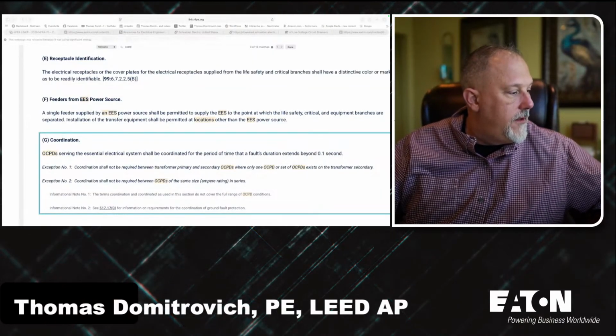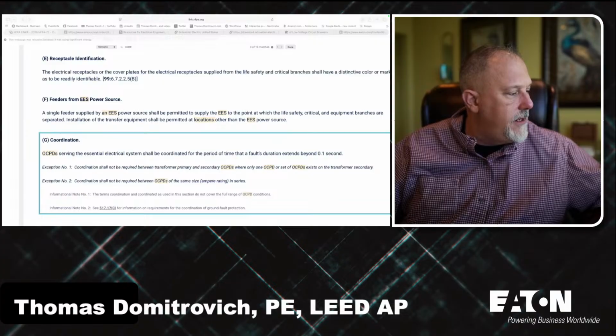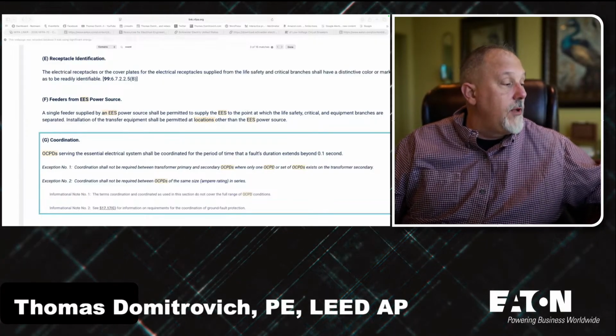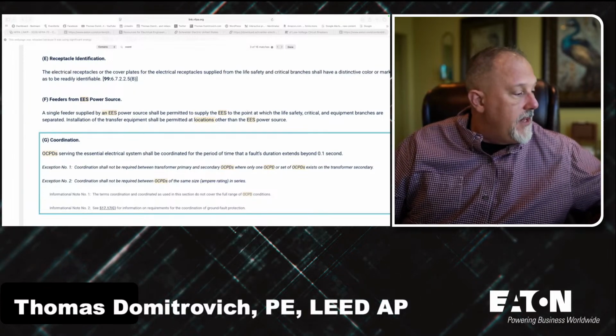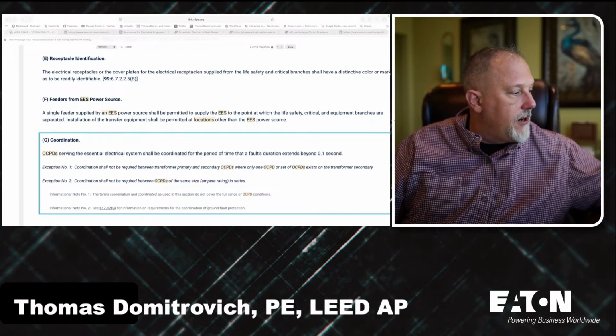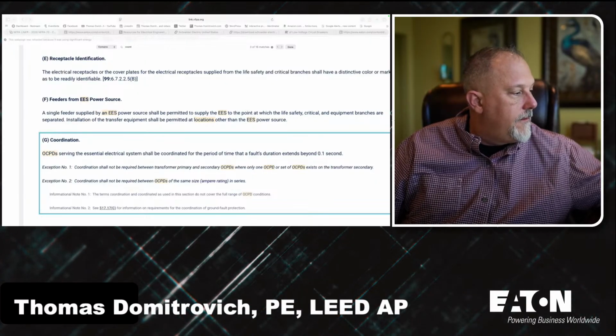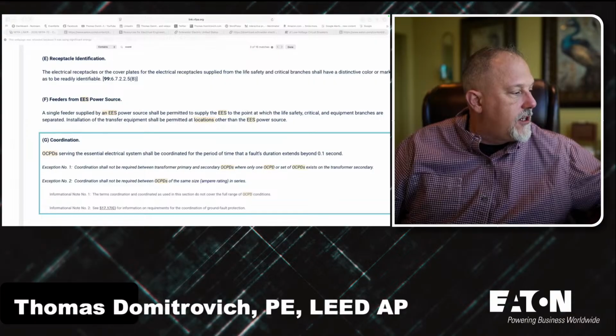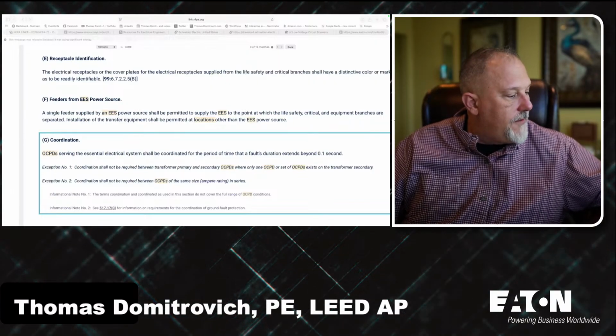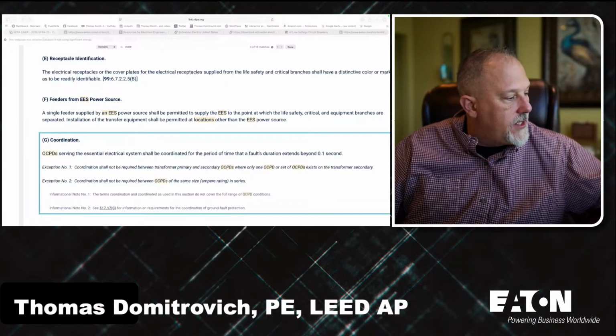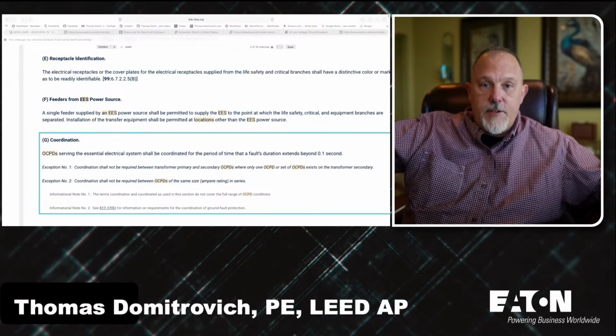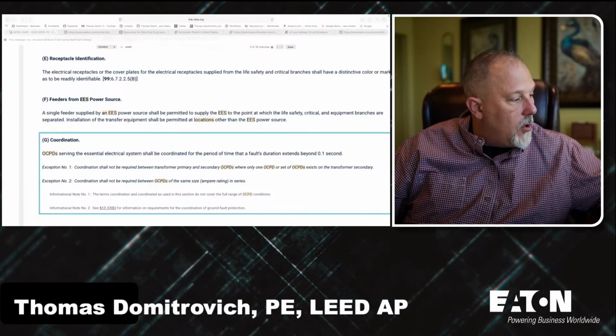All right, ground fault currents. Here's what I'll say on ground fault currents. These curves will respond to a ground fault current because remember, if I have a circuit breaker, in that circuit breaker, I've got 3 switches. If I have a ground fault current flowing through this, if I go upstream and I have a zero sequence CT, it's going to see it, but so will that pole.